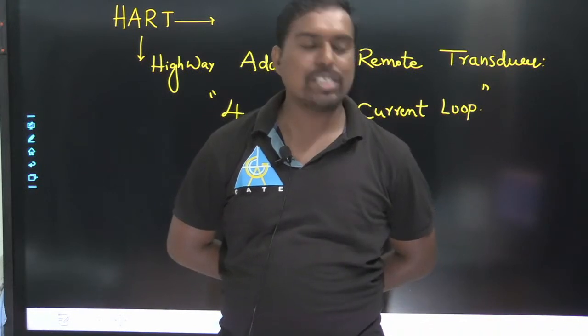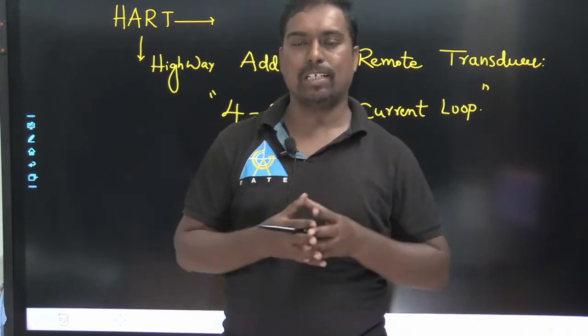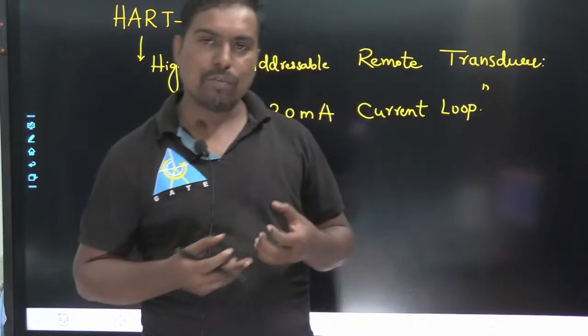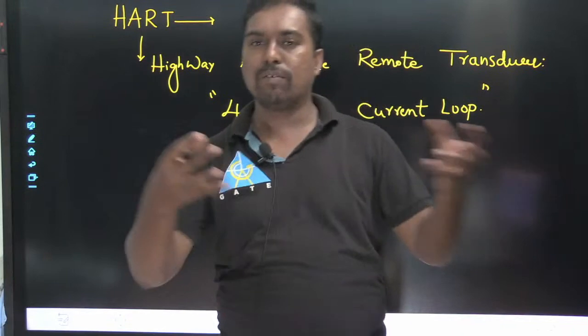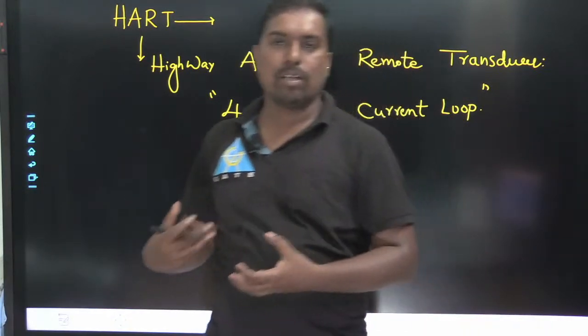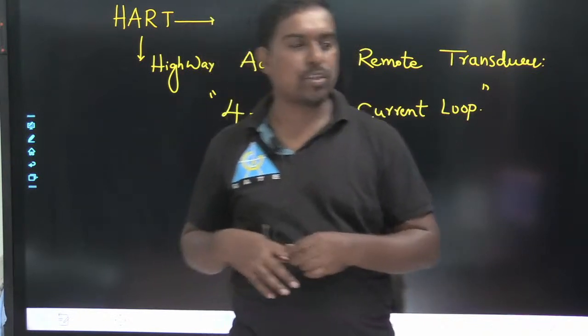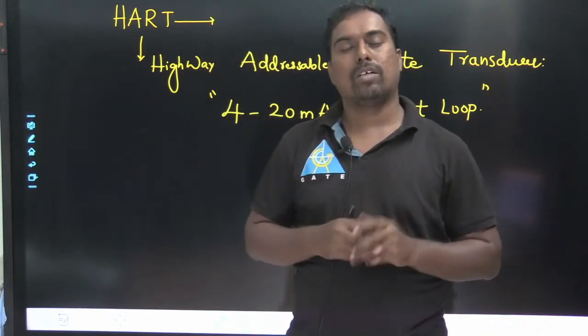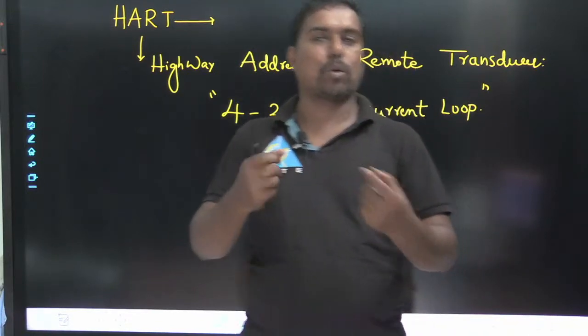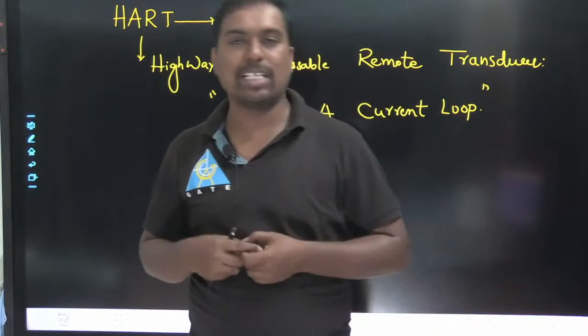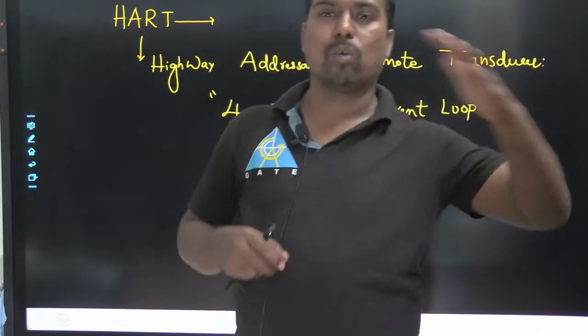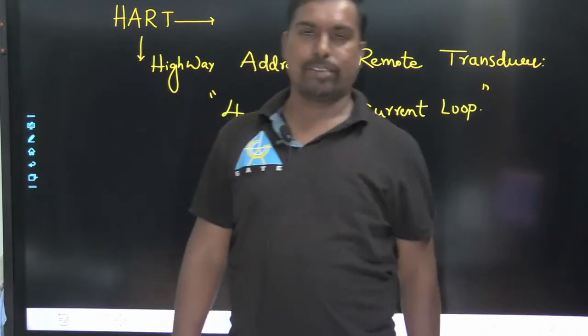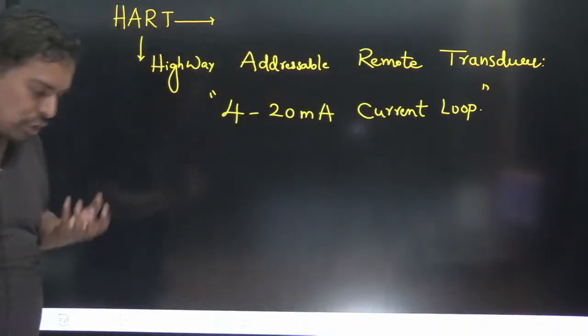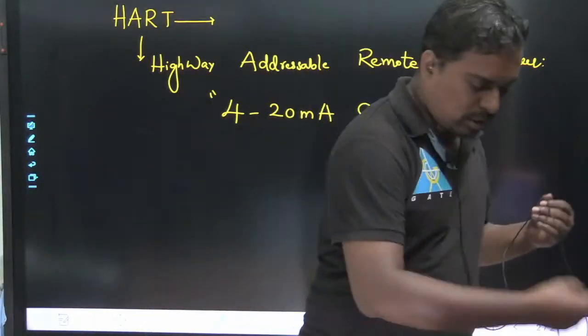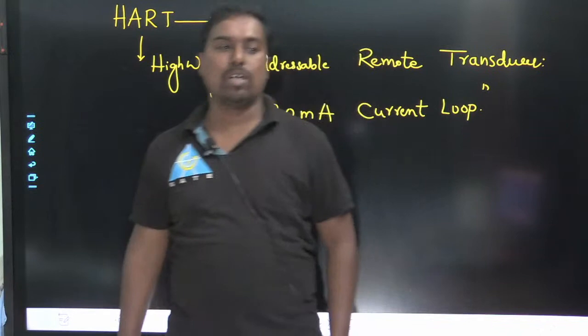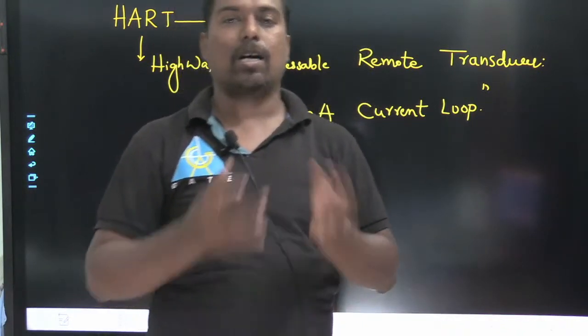So in industry, the fastest way of data transmission is digital. So if I want to communicate between field devices and a master in a sophisticated way, since this 4 to 20 milliamperes is always related to current, we have to use an open protocol which also enables digital data transmission over an analog wire. That is the HART. HART introduced the superimposition of a digital signal on the analog signal.